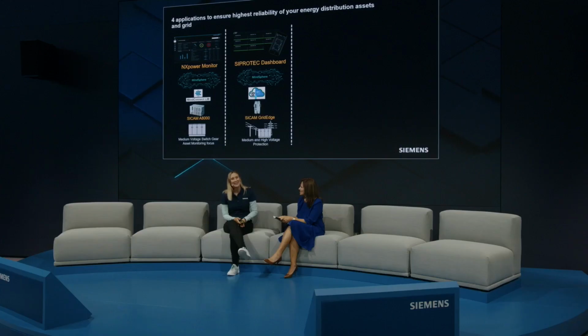The second application is the so-called SIPROTEC Dashboard, really focusing on the protection relay. With that, we can find failures really fast in the medium voltage network. The real advantage is that you also have documentation of changes in settings, changes of the fault record. For example, remember there's a trip, not a trip to go, but really a trip in the switchgear, and it's really hard to get the failures out.